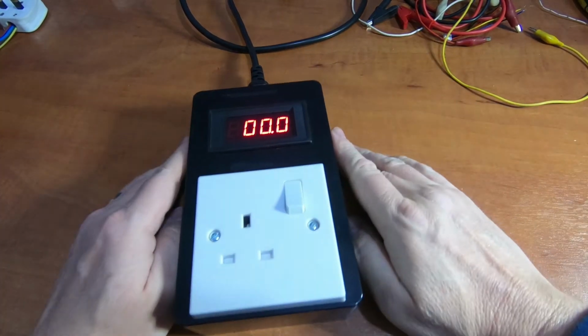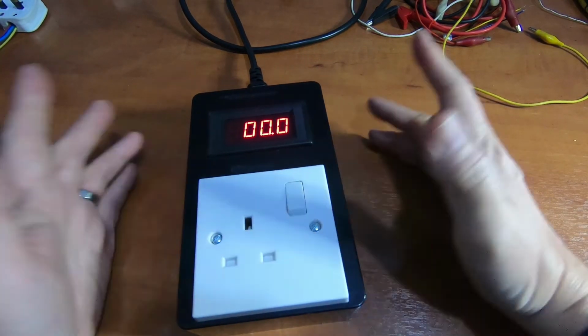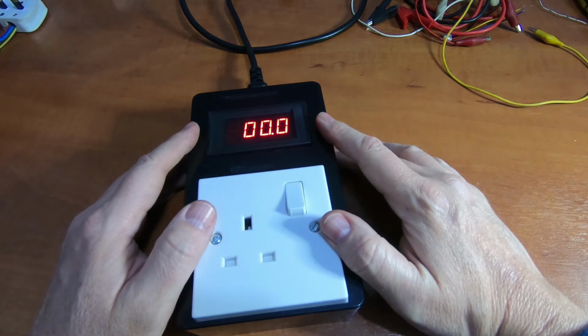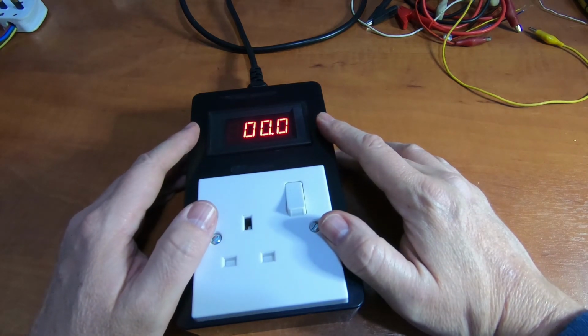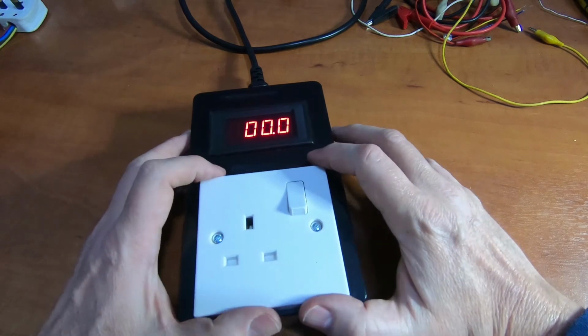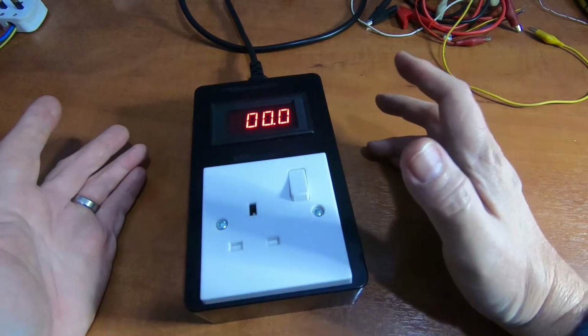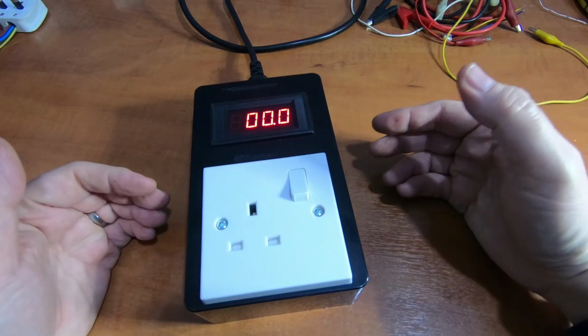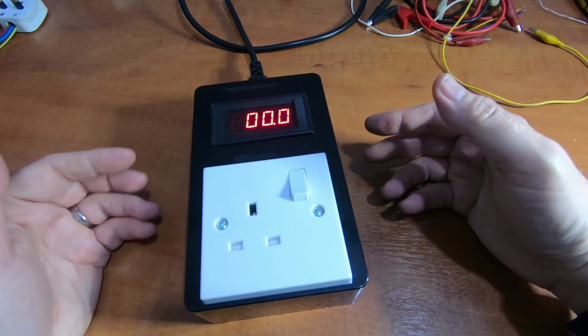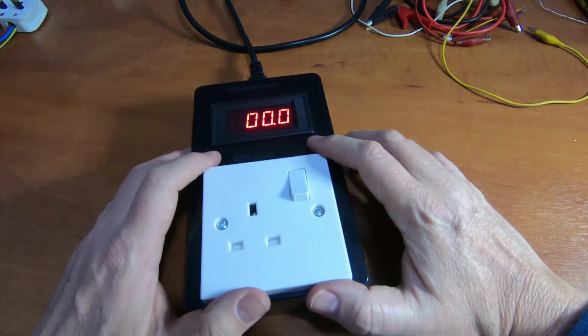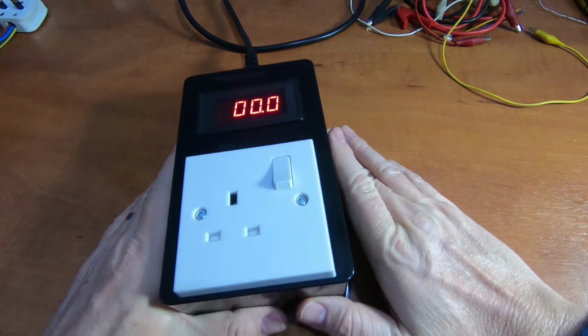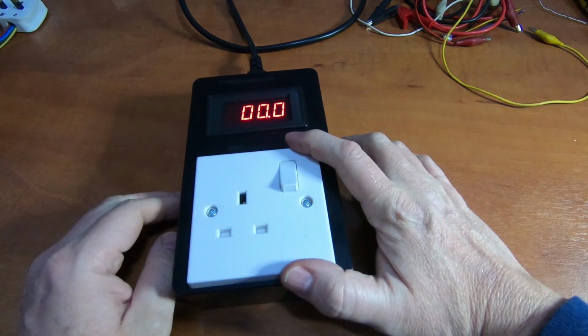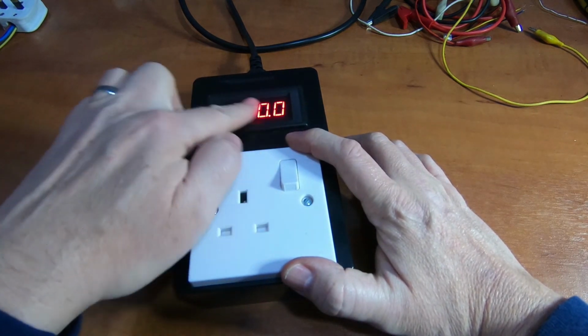This device is useful because if something is failing in the house, if your RCD, residual current detection, is tripping and you're not sure what it is, the usual method is you unplug everything, try again, plug some things back in, try again until you find out which item it is. Now with this device, you can go around the house, plug in all of your items into here, and look at what the earth leakage is.